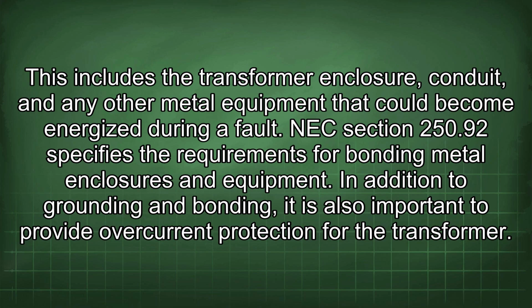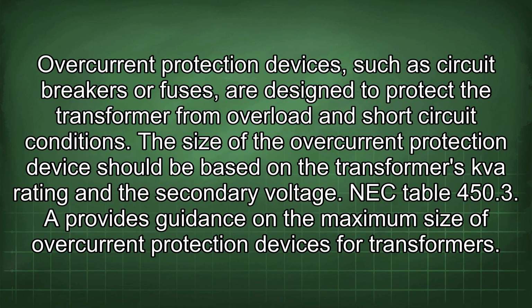In addition to grounding and bonding, it is also important to provide overcurrent protection for the transformer. Overcurrent protection devices, such as circuit breakers or fuses, are designed to protect the transformer from overload and short-circuit conditions. The size of the overcurrent protection device should be based on the transformer's kVA rating and the secondary voltage. NEC Table 450.3 provides guidance on the maximum size of overcurrent protection devices for transformers.